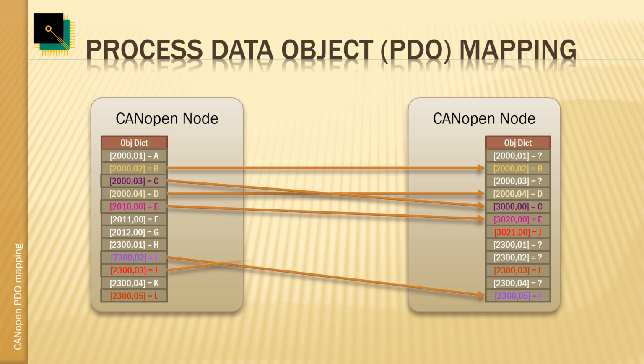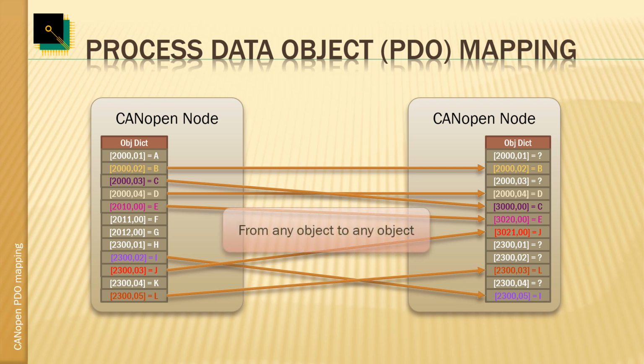The reason why this is used quite a lot is that if you use several same CANopen nodes as a transmitter, so maybe you have 5, 6, 7 sensors that all have the same object dictionary entry layout for their input data, and all this data needs to be merged into a single destination node, then of course in the destination node we need to have different entries for the data coming from different nodes. Otherwise they would overwrite each other.